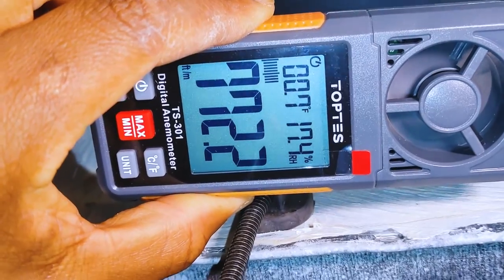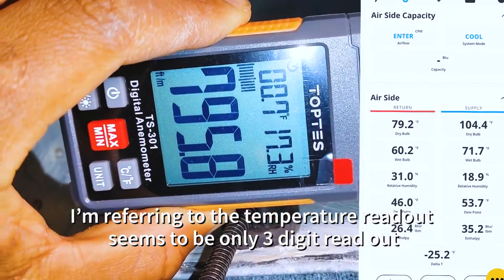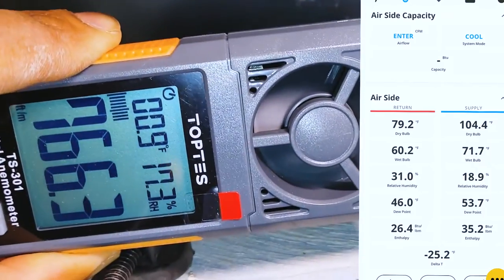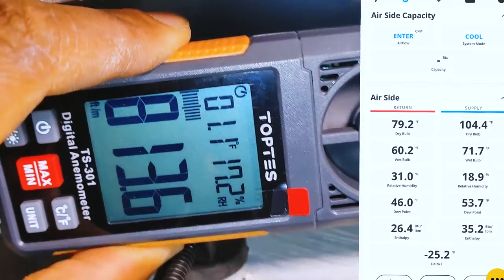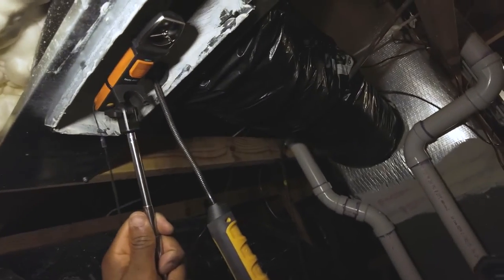One thing to note: once the temperature got past 100 degrees Fahrenheit, the TOPTES is showing 0.9 rather than 100.9, so there's a display rollover issue. Temperature and humidity readings are pretty much on par with my Fieldpiece psychrometer. I'll be reaching out to TOPTES about whether that's a factory setting or a unit issue. The Testo is reading around the same spot — about 740 feet per minute.